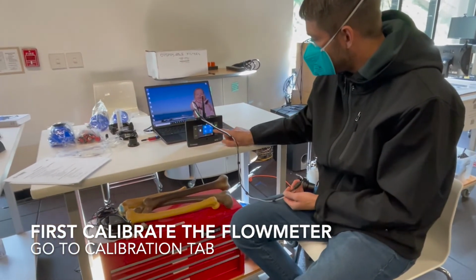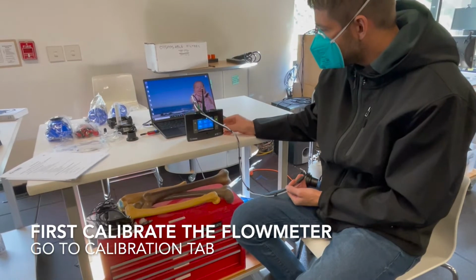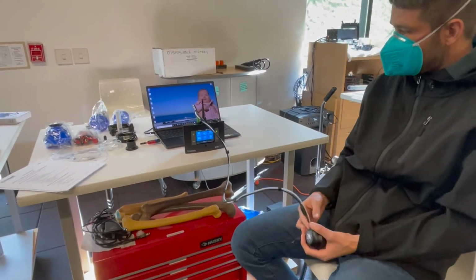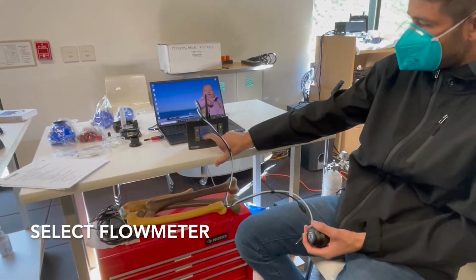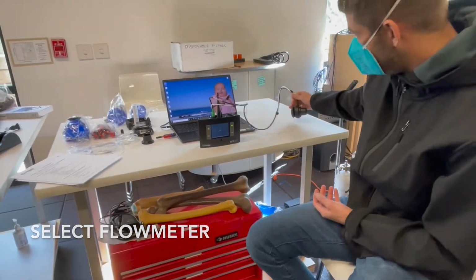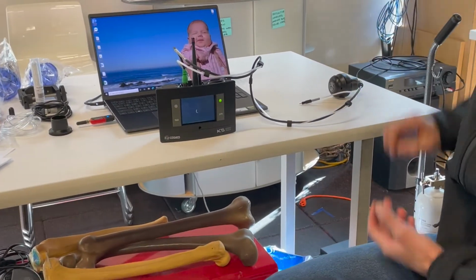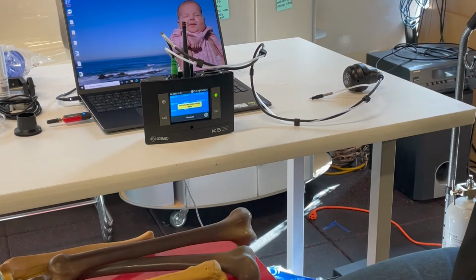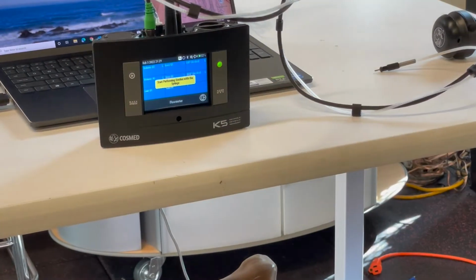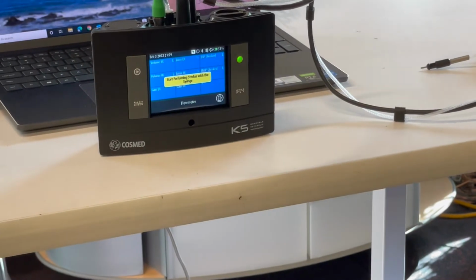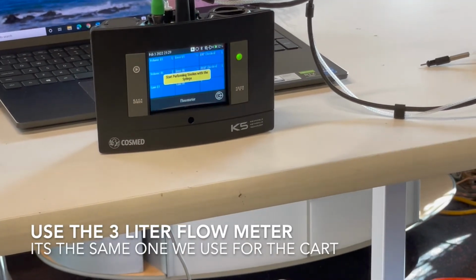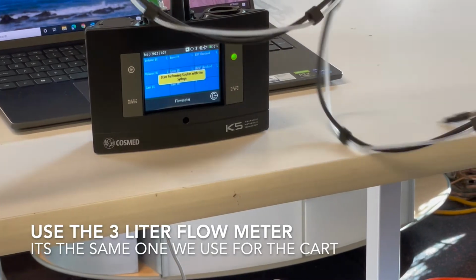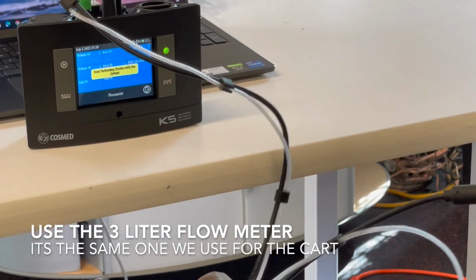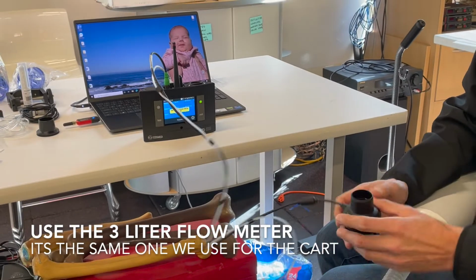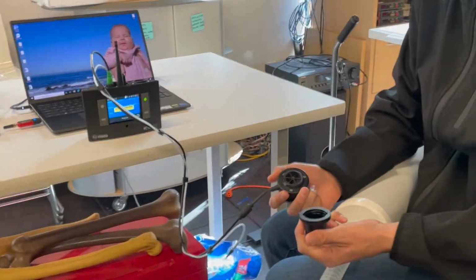Right here, we're just going to the calibration tab. The first thing we've got is flow meter. So we hit flow meter, and it's not going to tell us anything. It's just basically going to say start performing the strokes when you're ready, and you'll just go ahead and do that. We're using the same one as we do for the stationary cart. This is the adapter you need to do the calibration, and that just spins on like that.